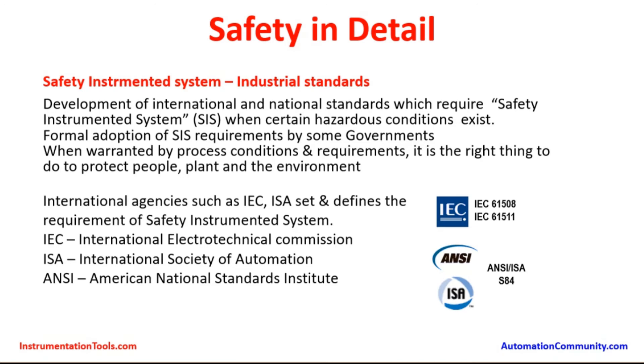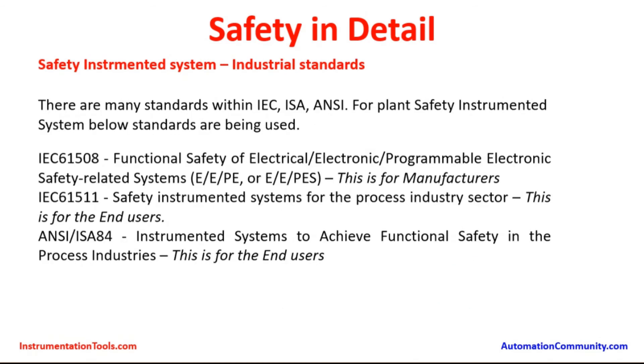International agencies such as IEC and ISA set and define the requirements of safety instrumented systems. IEC stands for International Electro-Technical Commission, ISA stands for International Society of Automation, and ANSI stands for American National Standards Institute. There are different standards within IEC, ISA, and ANSI for safety instrumented systems. One is IEC 61508, which covers functional safety of electrical, electronic, and programmable electronic safety-related systems — also known as E/E/PE or E/E/PES. This standard is used primarily by manufacturers producing electronic equipment, sensors, final control elements, and logic solvers.